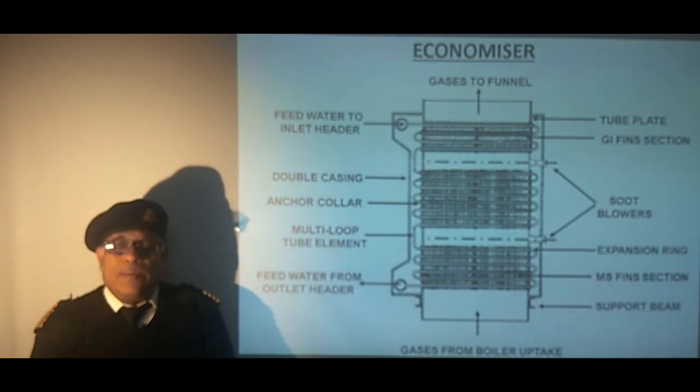Inlet header. Multi loop tube elements are fixed on one side with the anchor collar whereas other end is equipped with expansion ring which provides necessary expansion allowance. Inlet header is equipped with a vent to release air and outlet header with a drain to empty out the economizer. So this is a brief description of economizer.